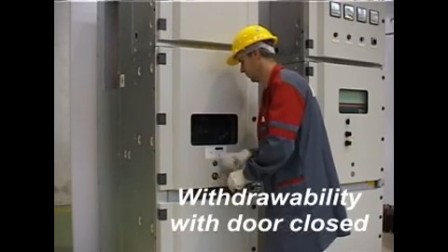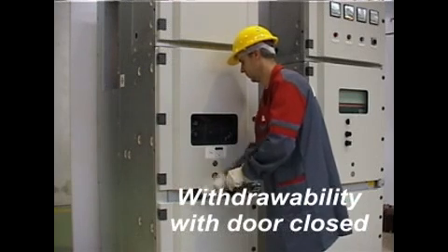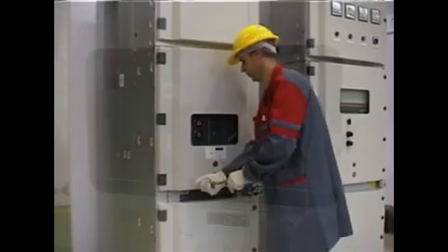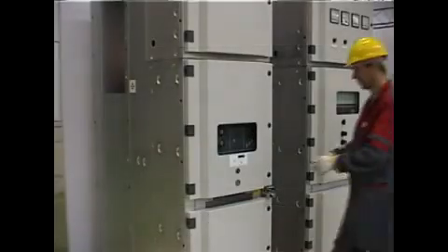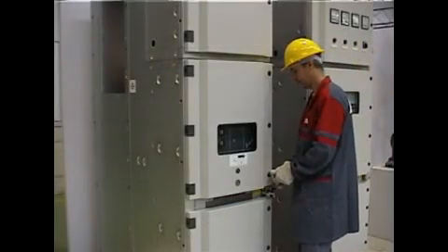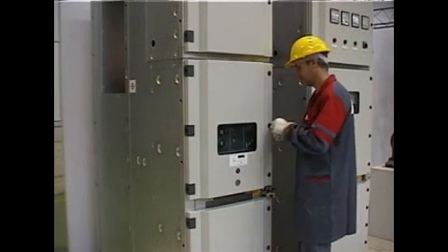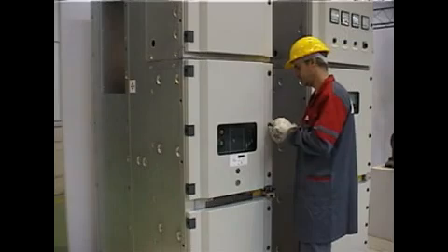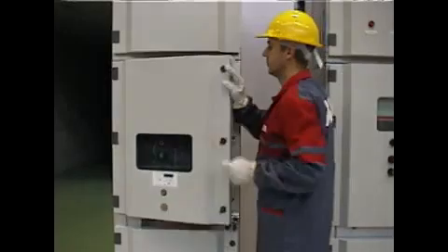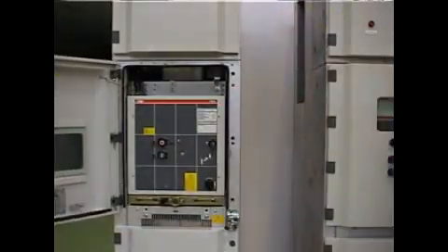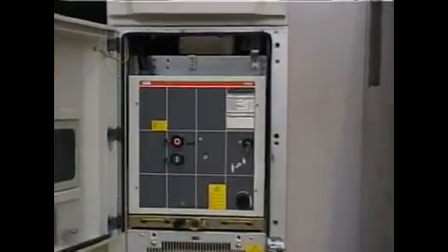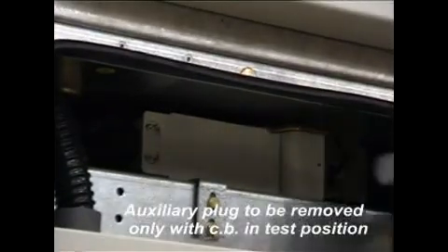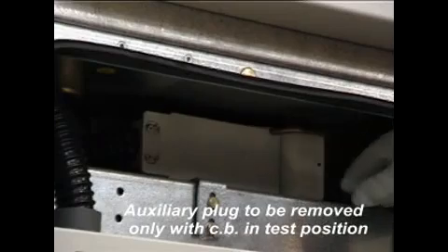At this point, the circuit breaker can be safely withdrawn in test position, and we will have the possibility to open the door. When the door is completely opened, we have a direct view of the circuit breaker operating mechanism with the auxiliary plug on the top, still connected to the switchboard. We can notice the interlock which prevents the auxiliary plug from being removed when the circuit breaker is not in fully withdrawn position.